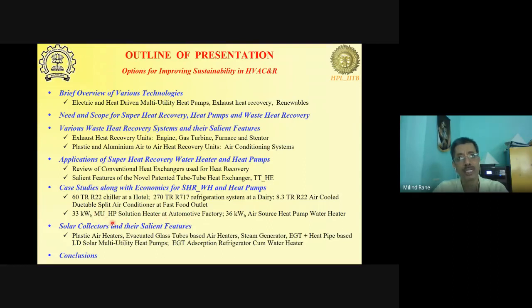Multi-utility means, normally if you look at an air conditioner, it either gives you air conditioning alone, or if it is a chiller, it produces chilled water alone as a useful utility. Now, there are heat pumps which can do heating in winter and cooling in summer and monsoon. But that also produces only one utility at a time, although it can generate both utilities during different periods of the year. Now, our multi-utility heat pumps concurrently generate more than one utility, and that too in a flexible manner.